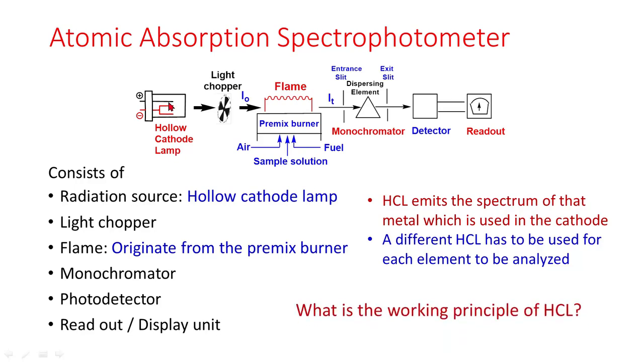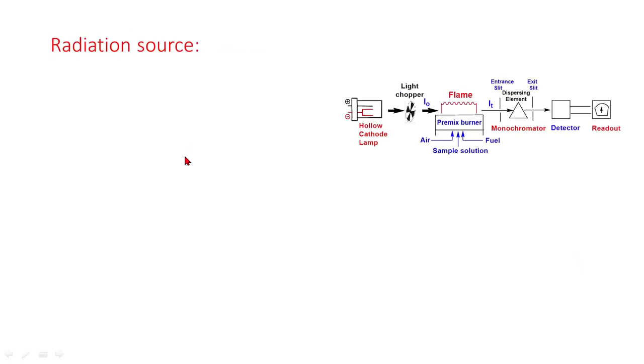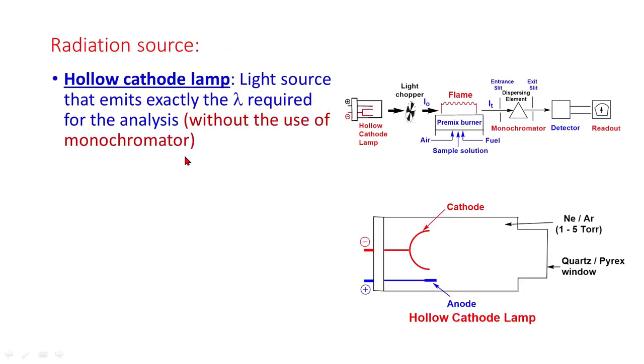What is the working principle of hollow cathode lamp? Hollow cathode lamp is a light source that emits exactly the wavelength required for analysis without the use of monochromator.